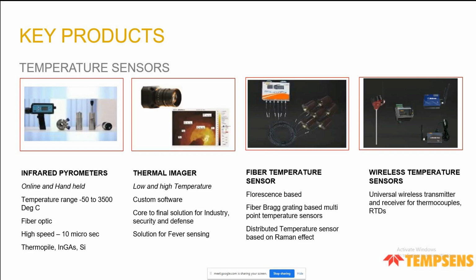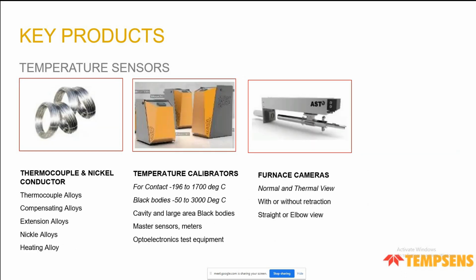We are also now offering wireless temperature transmitters and receivers. We have developed transmitters that can take input from thermocouples, RTDs or thermistors. They work on battery and connect directly to the receivers. Up to 50 transmitters can be connected to one receiver, and you can have multiple receivers for complete plant data acquisition, or for data logging. We are not currently offering this for control, mostly for data logging and monitoring temperature in various areas.